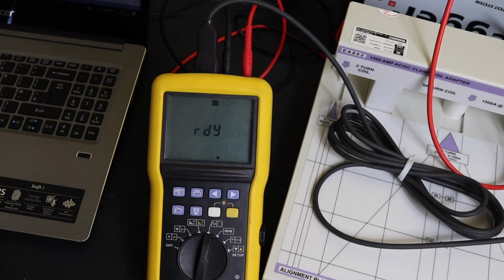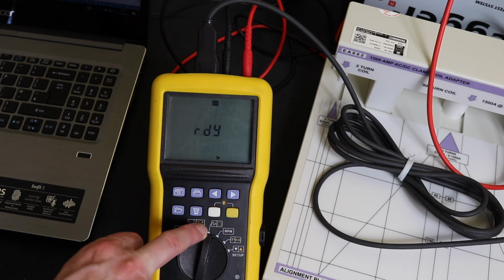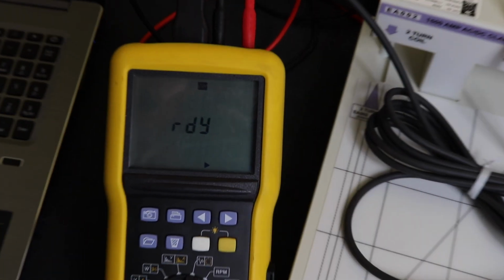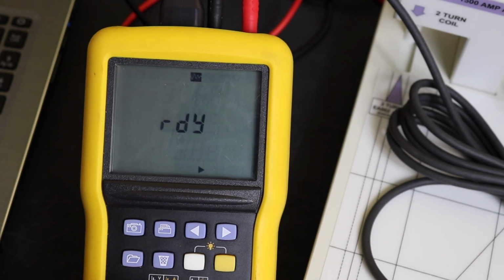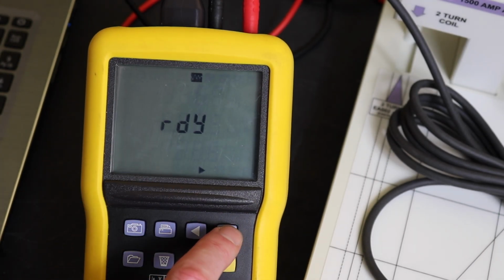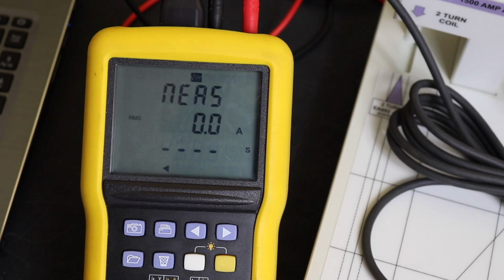So then going back to our actual function there, we can zoom in a little bit. So we're on the actual Inrush function. It sits to ready. What you're going to have to do is initialize it. So now it's sitting ready to record data. If I run the program, go there. So there you can see my 80 amp Inrush current. It's picked it up. 80 amps RMS, which is equivalent to 113.6 amps peak and 0.135 seconds, and that's all the data that you get with that.